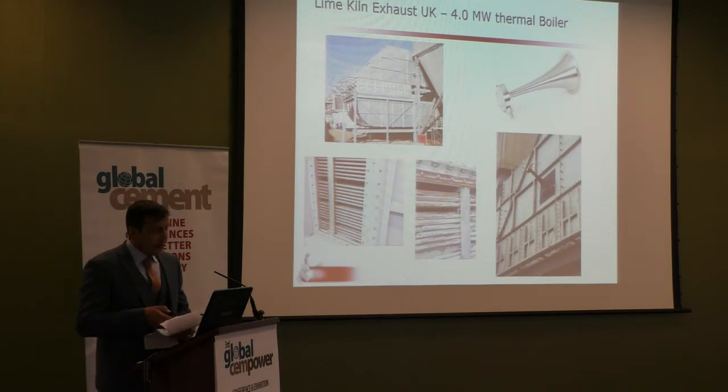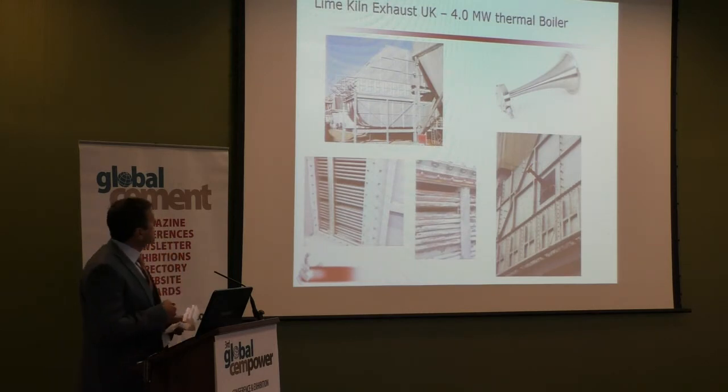So I mentioned earlier the issues that we've got with the dust. The ESP is on its way out, so we'll have higher dust loads than we would be seeing at the moment. But even so, we designed the system to have a hydraulic cleaning system. Between each one of the tubes is a stainless steel brush, and it would move backwards and forwards continuously on a hydraulic rack. When we installed it, as the corrosion built up, even on the stainless steel brushes, it started to jam. And those stainless steel brushes got to a point where the hydraulic ram wasn't strong enough to push the heat exchanger cleaning system along.